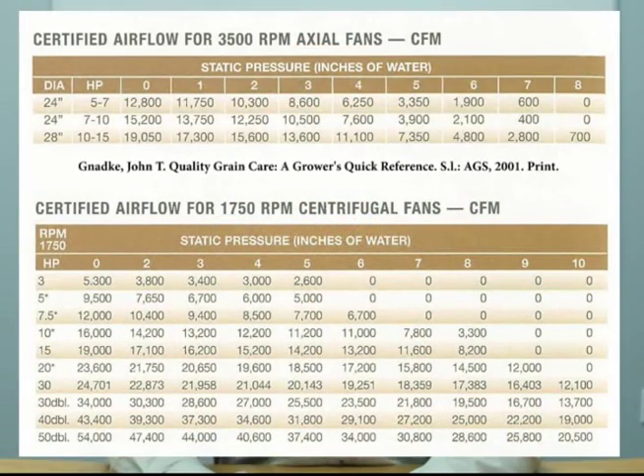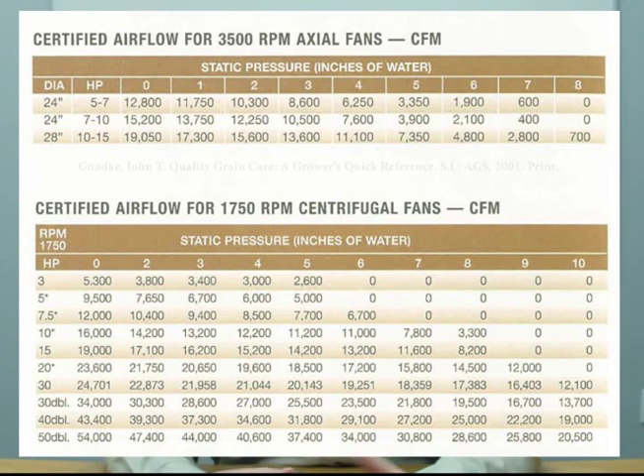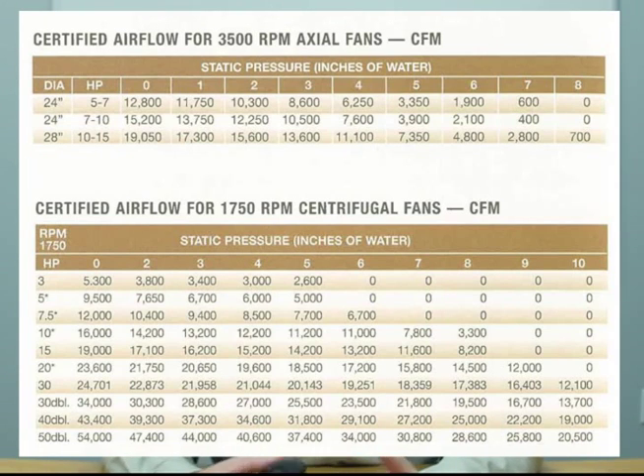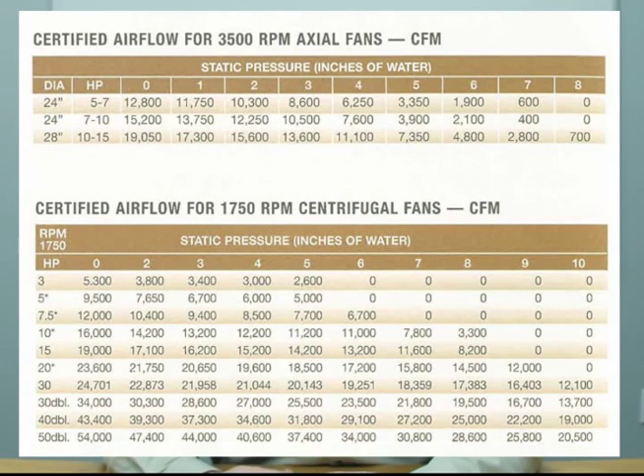On the two charts shown, there is one for axial vane fans and one for centrifugal fans. On the left side you choose what size of fan you have and the horsepower, and at the top of each chart is the static pressure. Knowing that static pressure and your fan horsepower, you can follow across and determine the total CFMs you have at that current depth of grain.